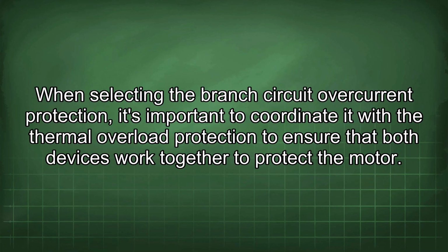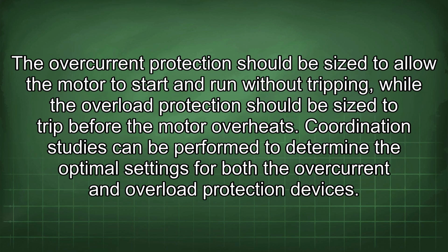When selecting the branch circuit overcurrent protection, it's important to coordinate it with the thermal overload protection to ensure that both devices work together to protect the motor. The overcurrent protection should be sized to allow the motor to start and run without tripping, while the overload protection should be sized to trip before the motor overheats. Coordination studies can be performed to determine the optimal settings for both the overcurrent and overload protection devices.